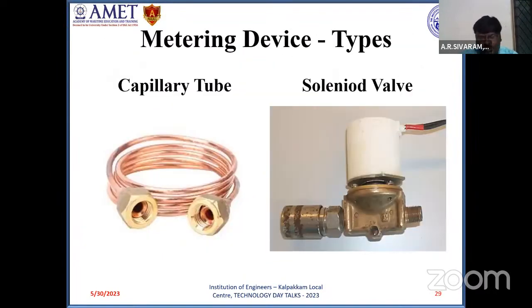And in the capillary tube, the expansion always takes place at the same rate because the cross-sectional area of the tube is uniform. Normally the capillary tube is used in refrigerators and of course in air conditioning systems up to 2 tons. Solenoid valves are employed in the case of large refrigeration systems. Even reefer containers used in marine refrigeration systems employ a combination of thermostatic expansion valve and solenoid valve. That is, two expansion devices are normally used in reefer containers. A reefer is a refrigerated container used to transport temperature sensitive cargo from one place to another.